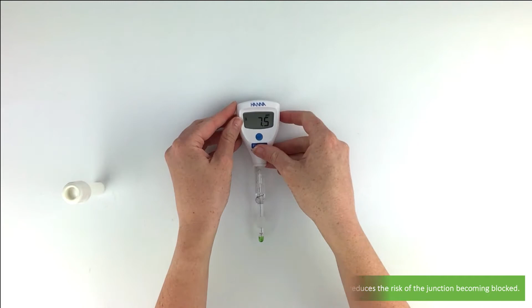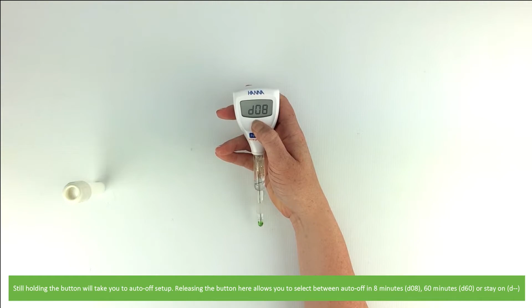Using the one button, you can perform a few different tasks. Pressing and releasing the button will turn the device on or off. Holding the button will cycle through to cal mode. Releasing the button here will enter calibration mode. Still holding the button will take you to auto off setup. Releasing the button here allows you to select between 8 minutes, 60 minutes, or to stay on. Press and release the button until you reach the desired settings. Then press and hold the button to confirm and exit the menu.